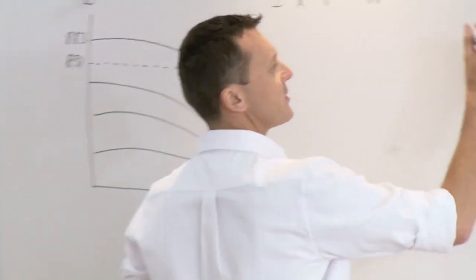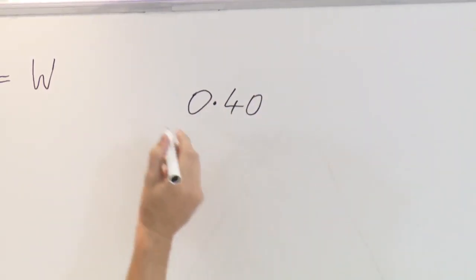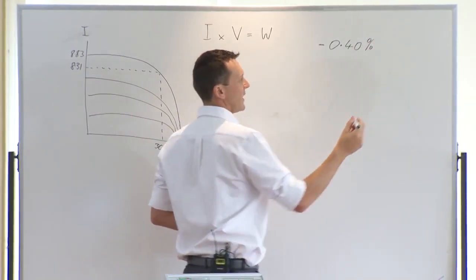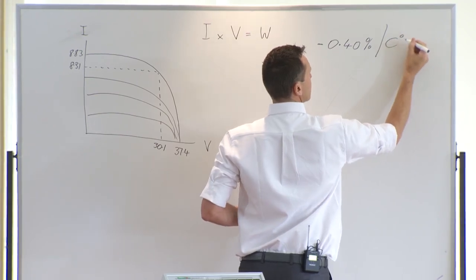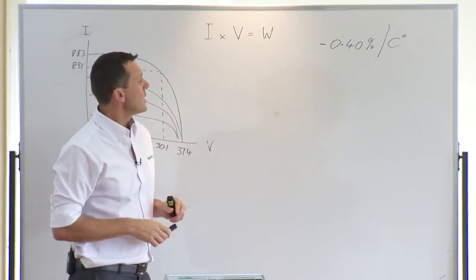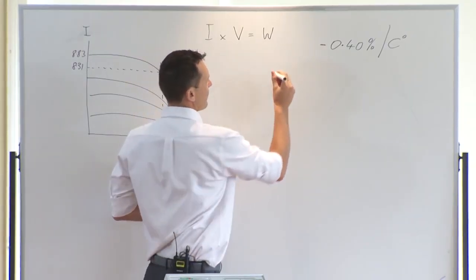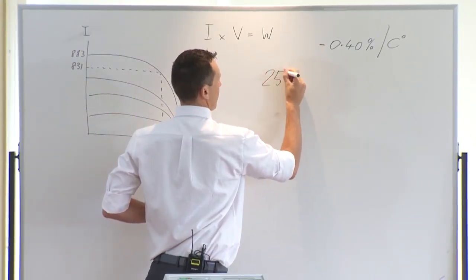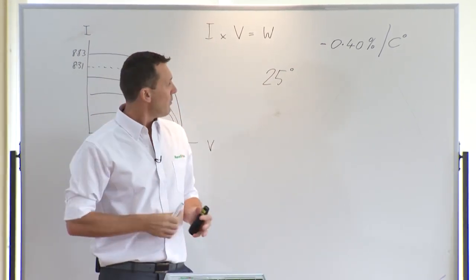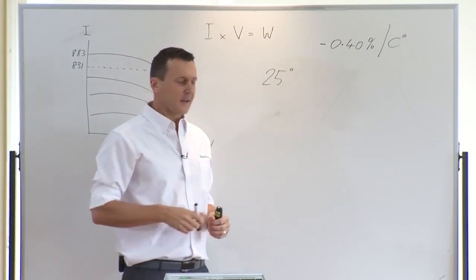So that temperature coefficient figure on our modules, 0.4, that's a negative figure, 0.4% per degree Celsius. That's what we're talking about with the coefficient. What that means is for every degree Celsius above 25 degrees, your system is going to, or that module, is going to lose 0.4 of a percent in output. So we'll just give you a working example of that.